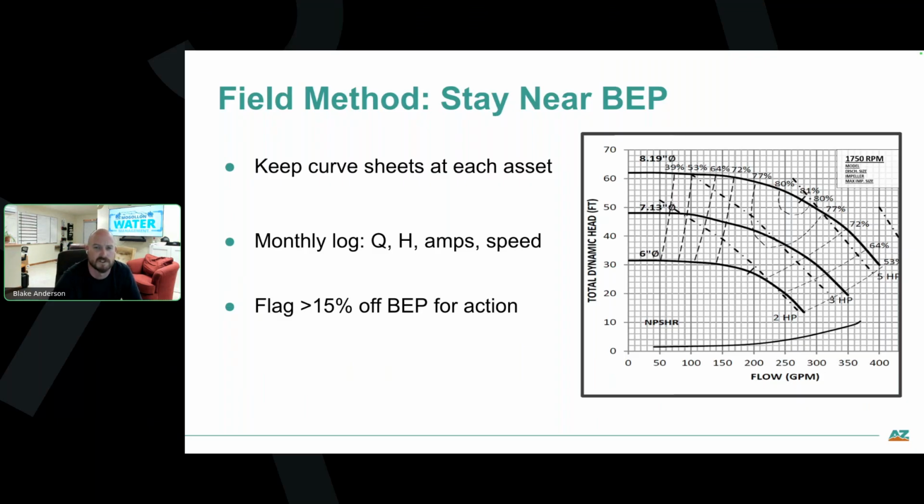So that best efficiency point is where your pump is the most efficient and really the happiest mechanically. If you sit far away from there, you're going to expect a lot higher energy use. You can get into heat and vibration. There could be a lot of problems that come with having the wrong size pump for the wrong application.